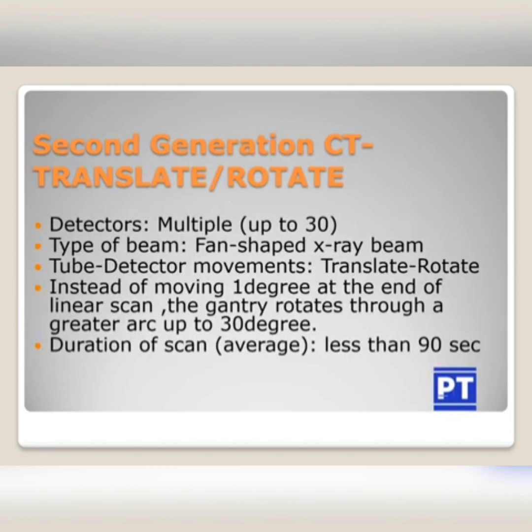Moving on to the second generation CT — it is also known as translate-rotate, the same movement type as the first generation CT, but it is different. From a single detector, the detectors increased to multiple — up to 30 detectors. The type of beam changed from a pencil beam to a fan-shaped X-ray beam. The tube-detector movement is the same translate-rotate, but instead of moving 1 degree at the end of a linear scan, the gantry rotates through a greater arc — up to 30 degrees.